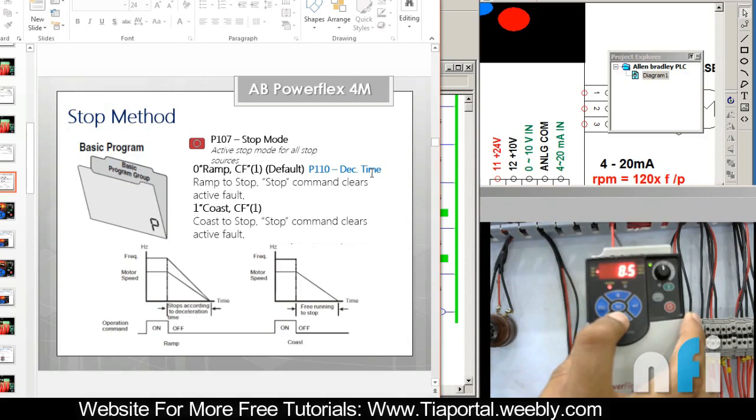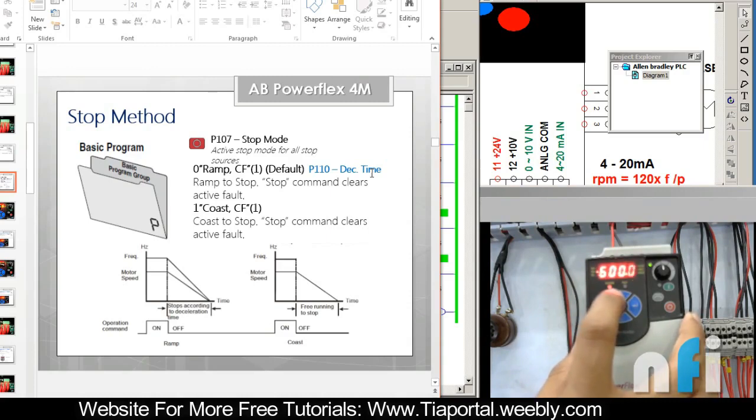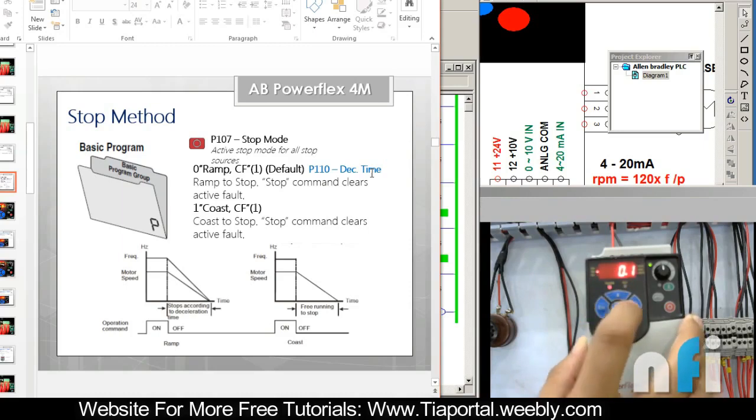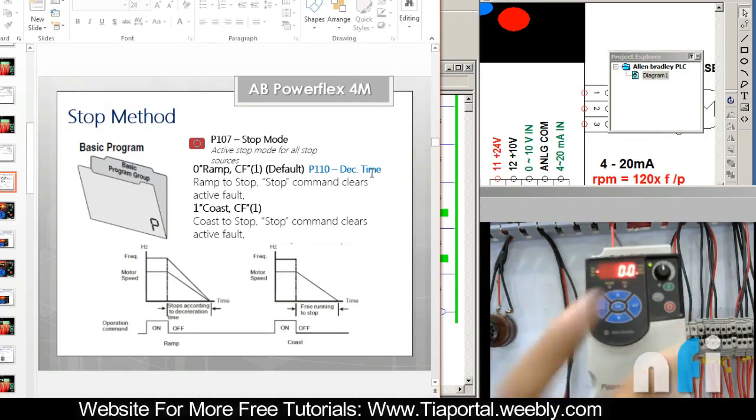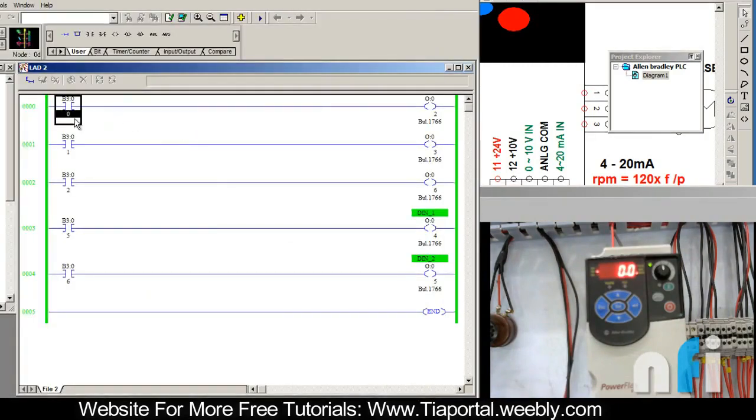Let me just reduce that to minimum. This is the maximum range which is 600 seconds. Unit is second, so minimum is 0.1. Now you'll find a noticeable difference. Let me start the drive again.